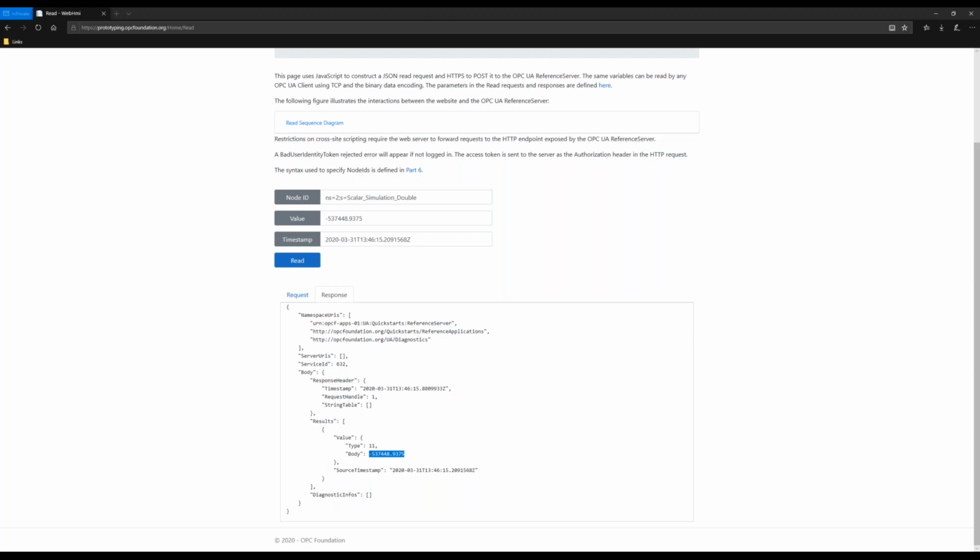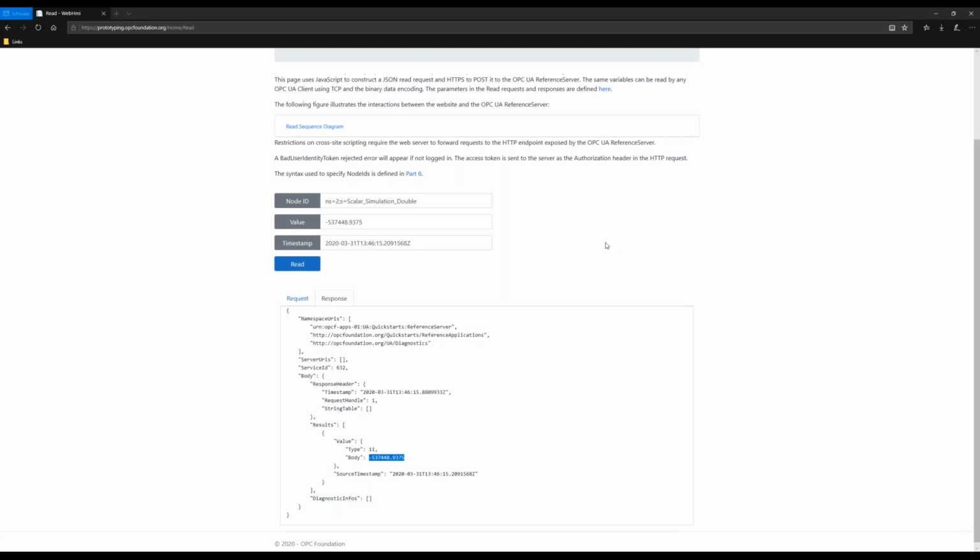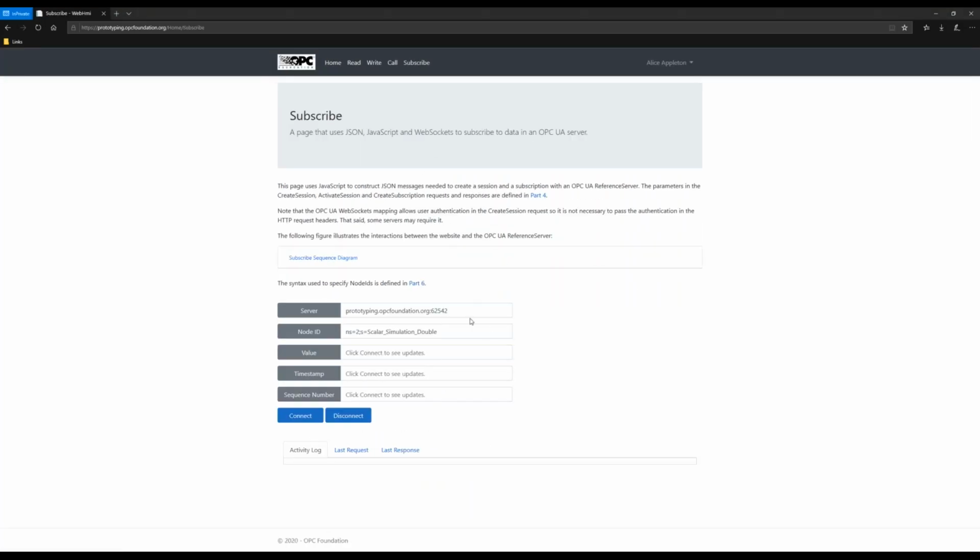In this demo, have you permitted the Opc Ua server to transmit through the firewall? Yes, for purposes of the WebSocket, if we go here, you'll see an additional port. This port has been opened. With WebSockets, you can also tunnel it through port 443, and I have done this with previous demos, where you're going back to the original server. For this case, I wanted to show connections. I was testing different connections to different servers, so each one of them ended up with a different port, but there's no requirement that you have to be using a different port.